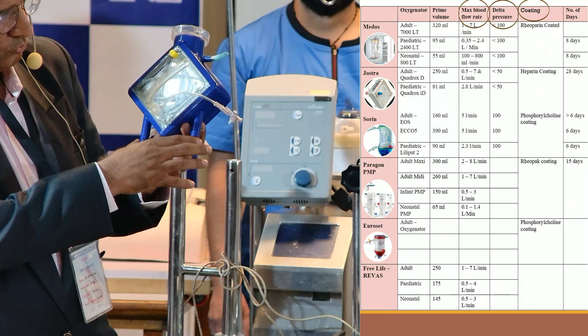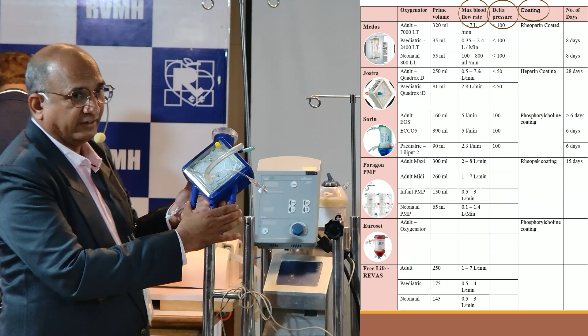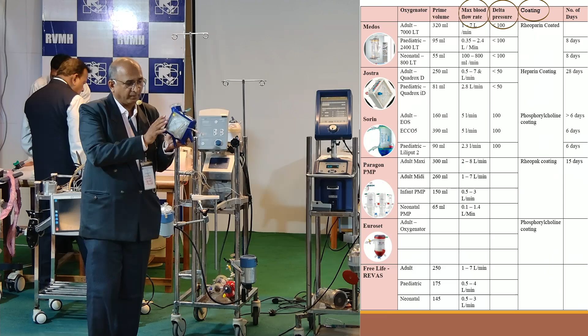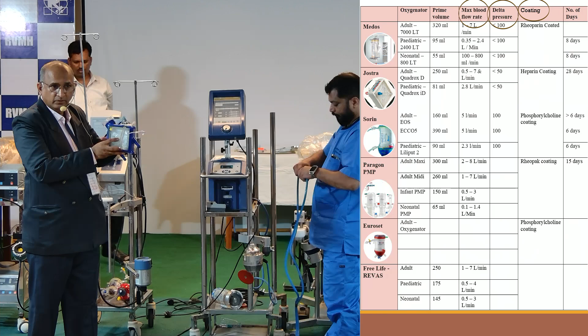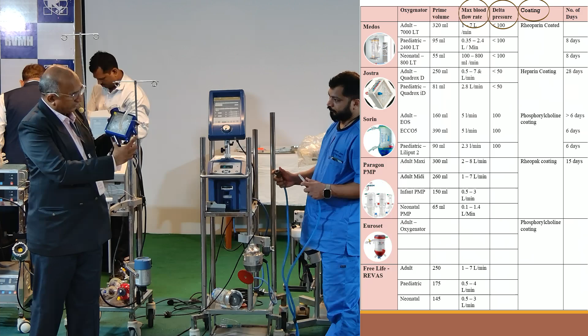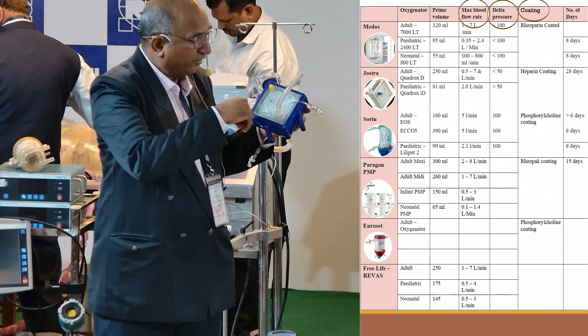Then these are the two for the heat exchanger, so the heater unit gets connected here. See, there are 3 compartments in this. In the oxygenator there are 3 compartments. One is the blood compartment. So blood is moving from here, it is going out from here. This is the blood compartment. And these are airtight compartments, so nothing can mix in it. There is another compartment which is running outside in the periphery, the water compartment. So that runs in the periphery.